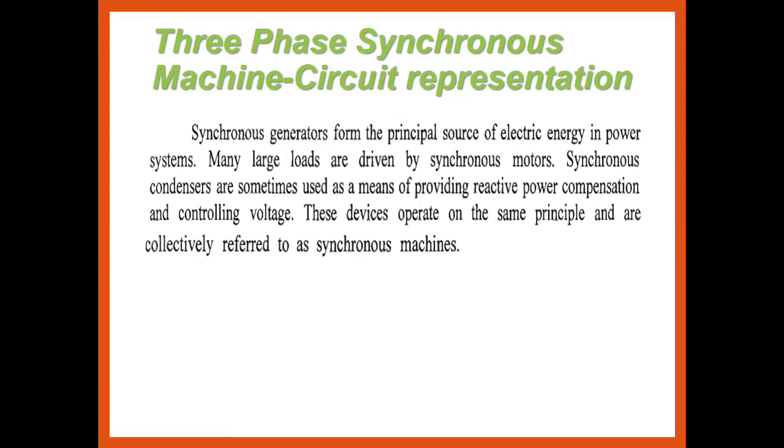If synchronization is not maintained, meaning the rotor speed becomes lower, the rotor flux lags compared to the stator flux, then it works as an asynchronous machine. In that case, there is poor power factor, reactive power compensation is affected, and voltage control is affected.